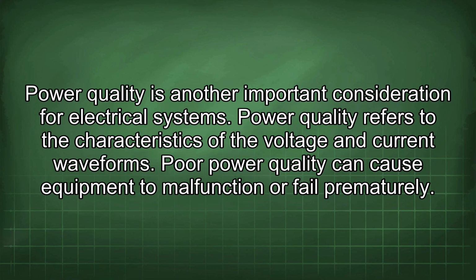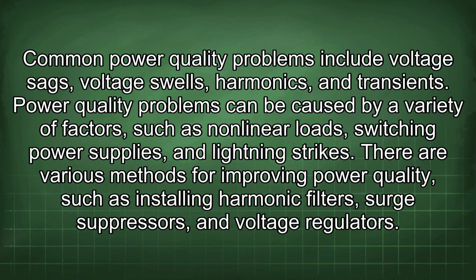Power quality is another important consideration for electrical systems. Power quality refers to the characteristics of the voltage and current waveforms. Poor power quality can cause equipment to malfunction or fail prematurely. Common power quality problems include voltage sags, voltage swells, harmonics, and transients. Power quality problems can be caused by a variety of factors, such as nonlinear loads, switching power supplies, and lightning strikes. There are various methods for improving power quality, such as installing harmonic filters, surge suppressors, and voltage regulators.